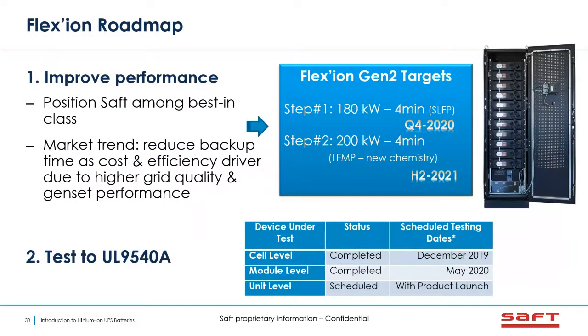A little bit about our roadmap: there are two main reasons for developing our next gen product. One is to improve safety, and the other is to position ourselves to be best in class in power. We know the market trend is to reduce backup time, reduce cost, drive efficiency with greater performance, and gensets are also improving their performance. So the goal is that this year we'll launch a battery cabinet that can reach 180 kilowatts for 4 minutes, available around September-October timeframe. Next year, second half, we'll introduce a new chemistry that gets us up to 200 kW for 4 minutes of power per cabinet.